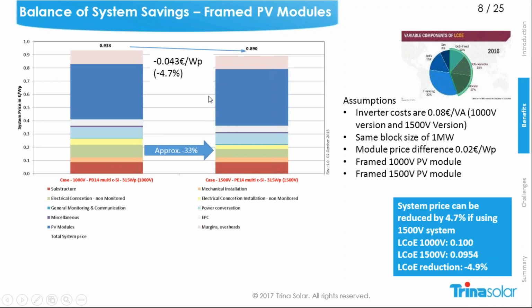This leads to a savings of approximately 4.3 cents, which is 4.7% relative, based on an LCOE calculation for a European country. There we can reduce LCOE by approximately 4.9%. That means if you compare a 1000 volt system with a 1500 volt system, the 1500 volt system, even with more expensive components, will lead to a cost advantage on a system level and on the capex level, which leads to lower LCOE and an increased profit.